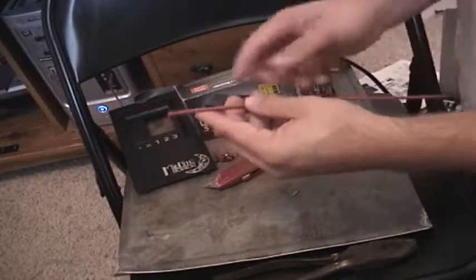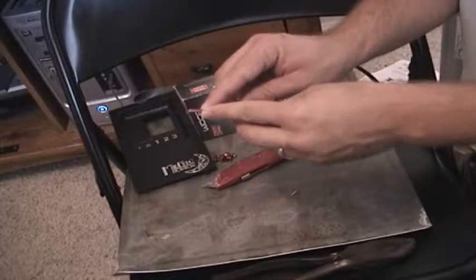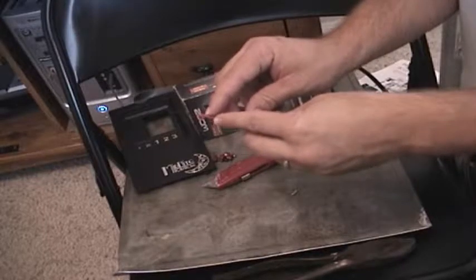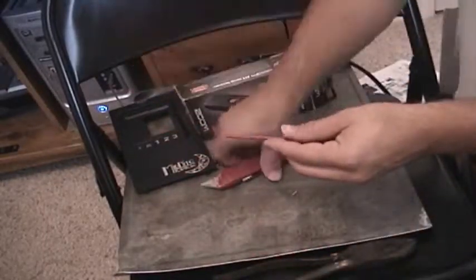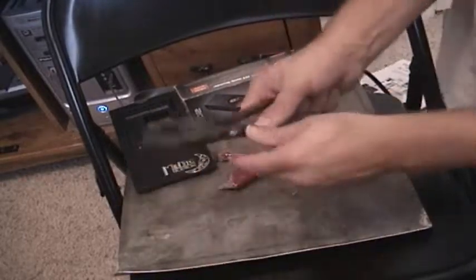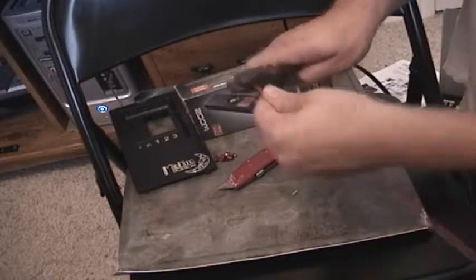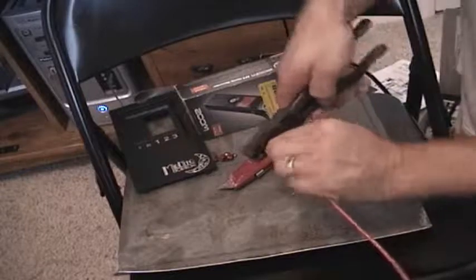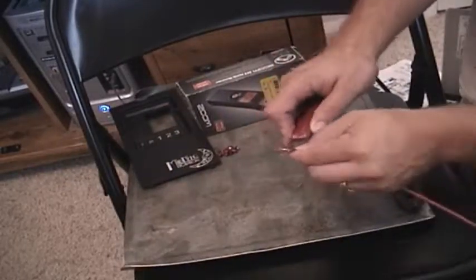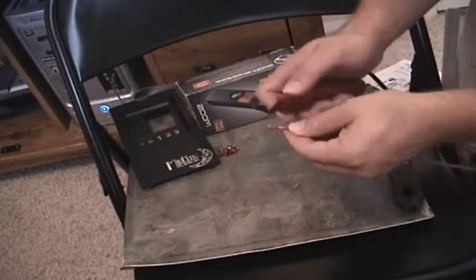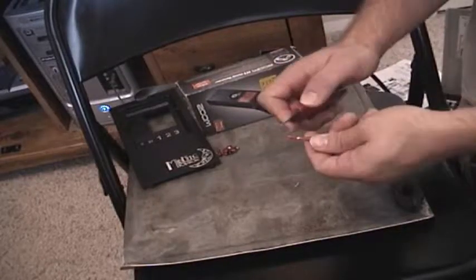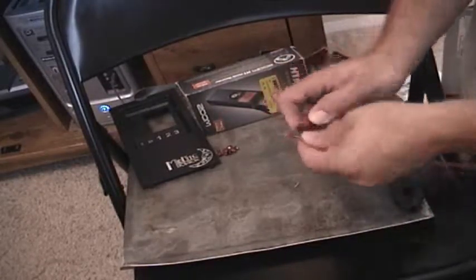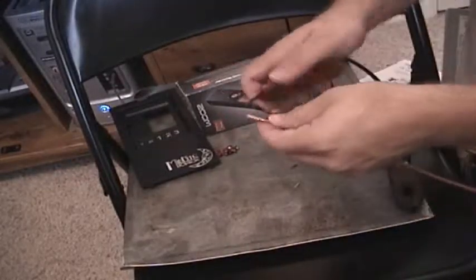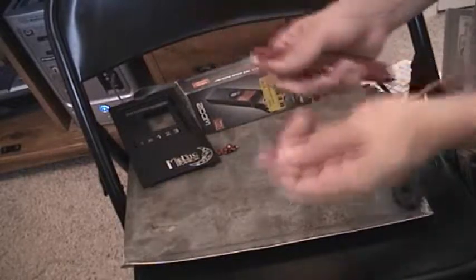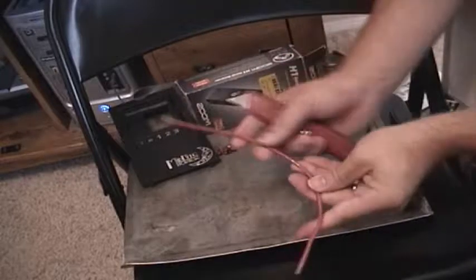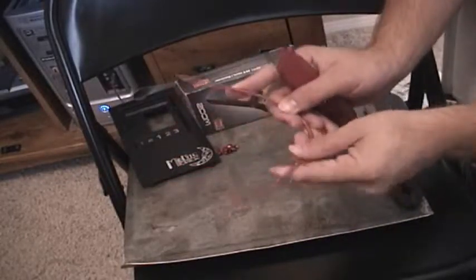Okay, looks good. And again, like we did on the other 2 wires, let's remove 1/2 inch of the skin from the end of both sides of this wire. And we can do this using the utility knife, or we can use our wire cutters. Just keep playing with it until you get that 1/2 inch of skin off both ends. Remember, don't cut into the conductor. Okay, now we're ready to install this red piece of 10 gauge wire into our combiner box.